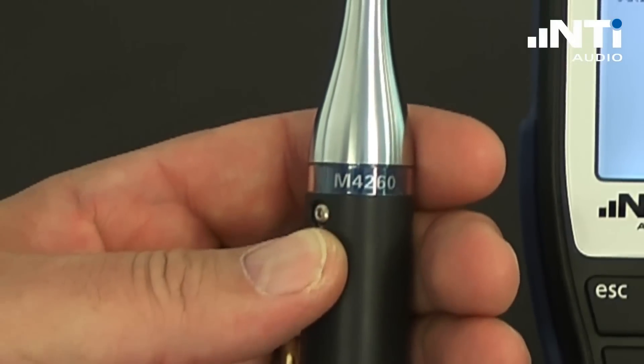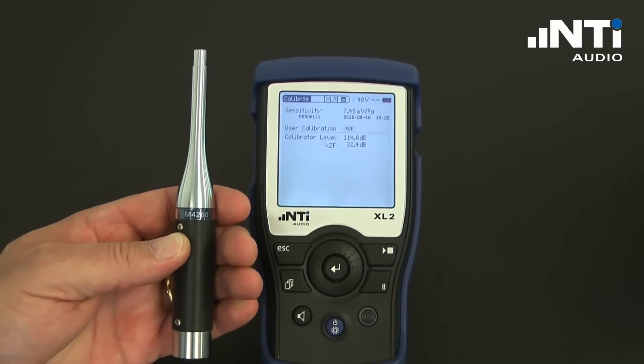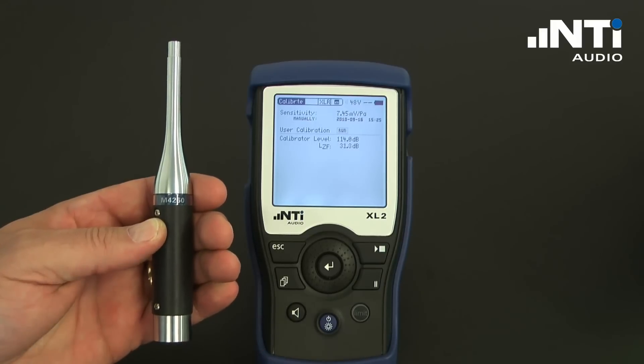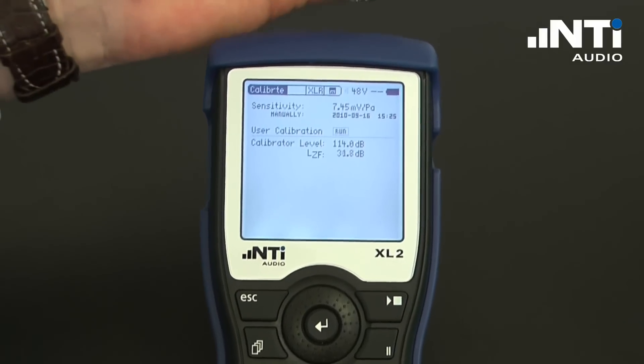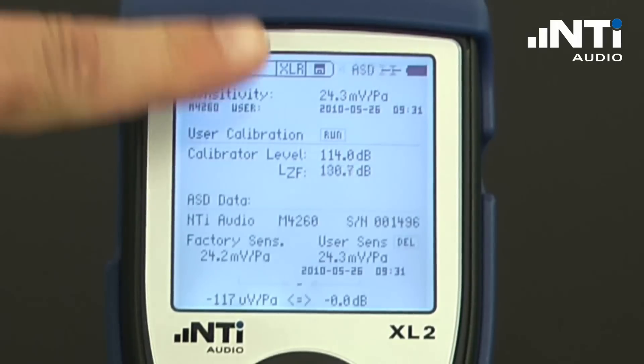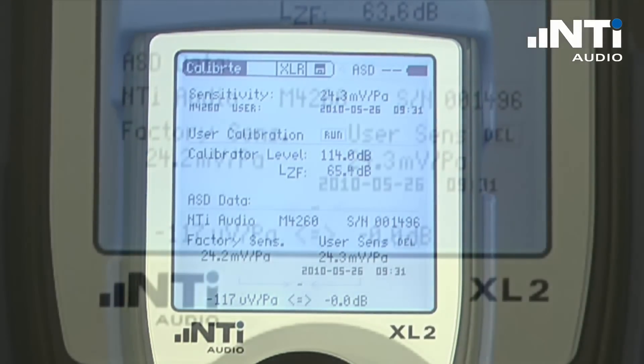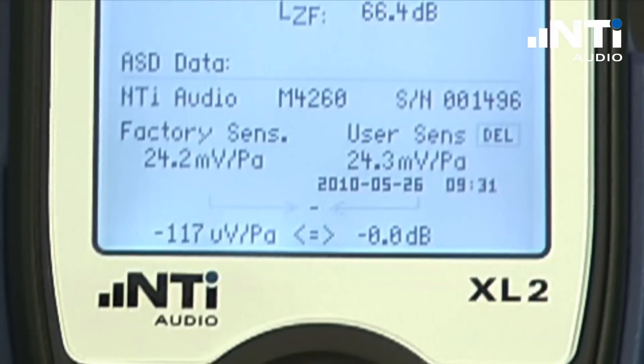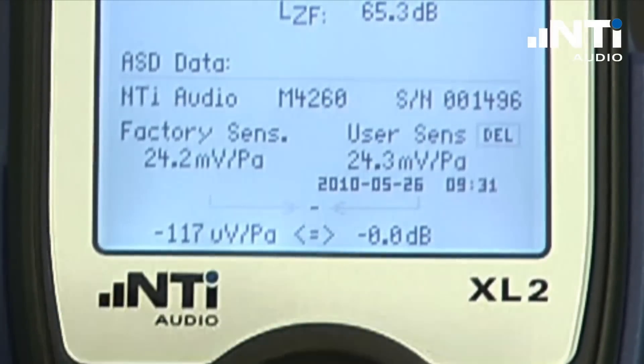The M-series measurement microphones feature an automatic sensor detector that reads the previously stored calibration data out of the microphone into the measurement instrument. As soon as we connect this microphone, it switches over to ASD and reads all the calibration data out of the measurement microphone, including the factory calibration and the last user calibration together with the measurement date and time.